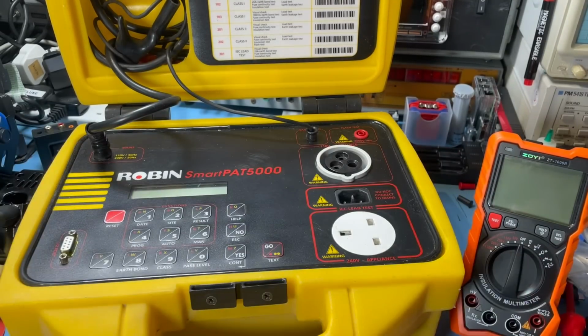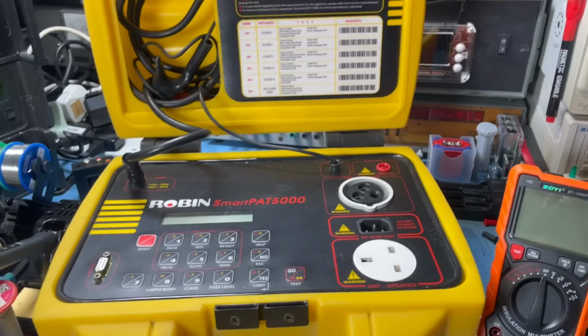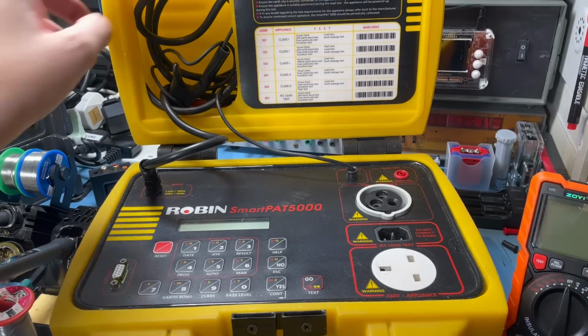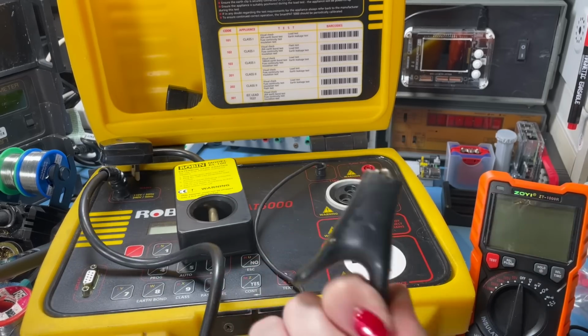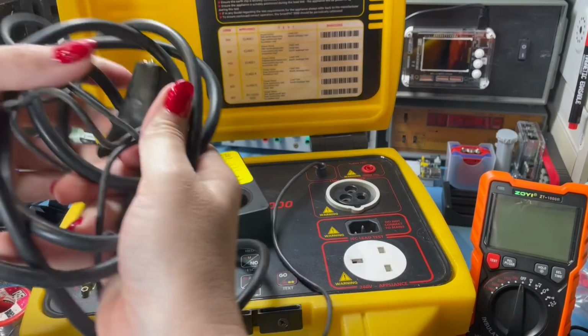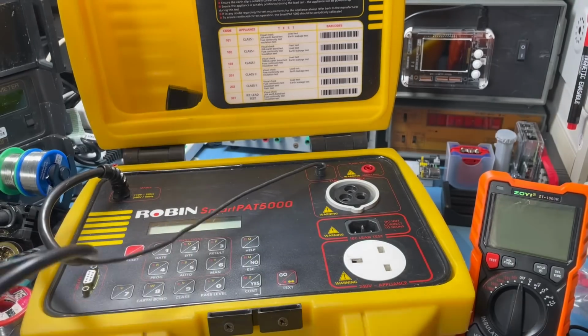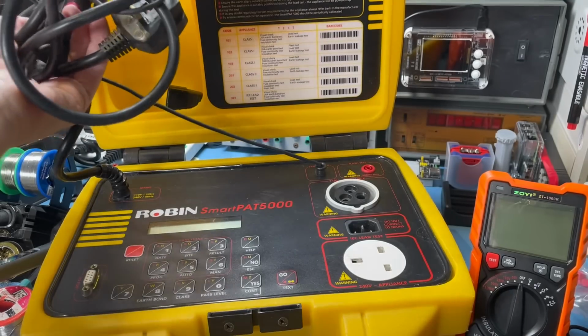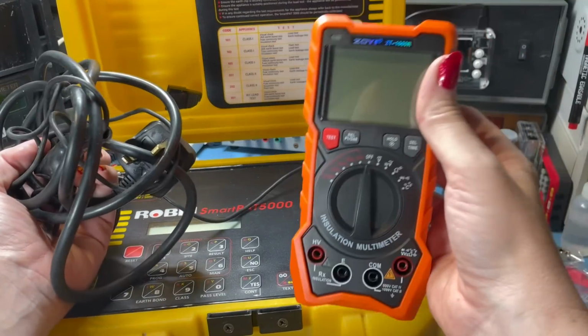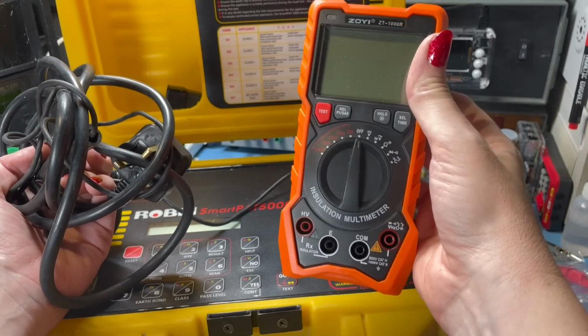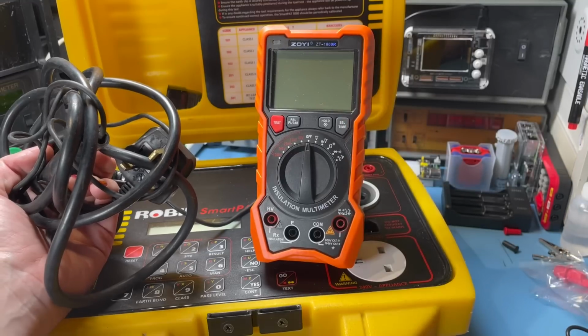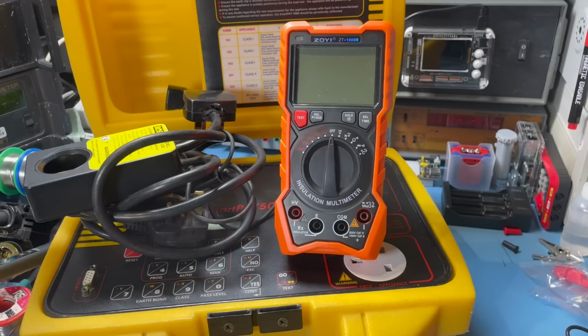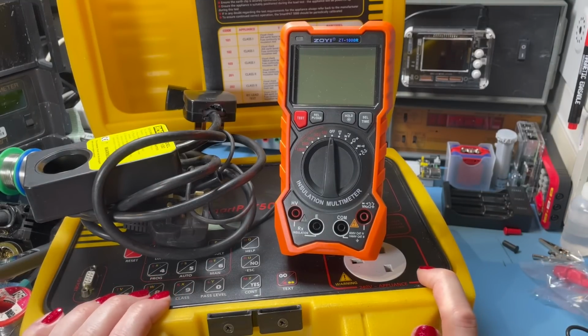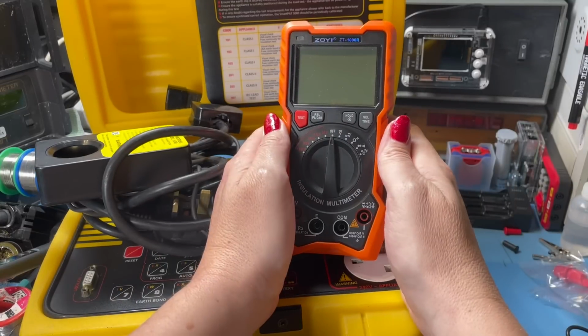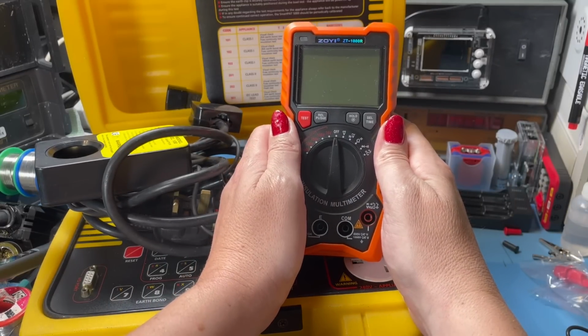This is what I generally would use for testing small appliances, office stuff, and disco equipment, amplifiers, that sort of stuff. Done a lot of PAT testing on those over the years. And I've got my earth clip here that goes onto it, the bulky thing I would use to test the insulation on an appliance. So it's got me thinking, can we use this to test the insulation of an appliance? Of course we can. I haven't really got the setup here for testing things like consumer units and DIN rails, but we have appliances and cables we can test, so let's have a go.